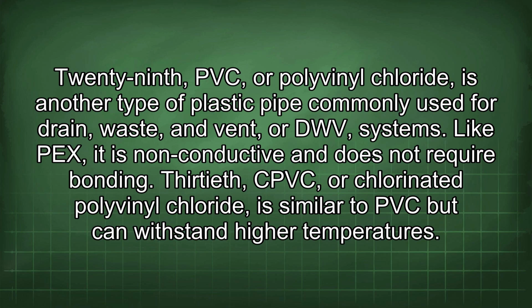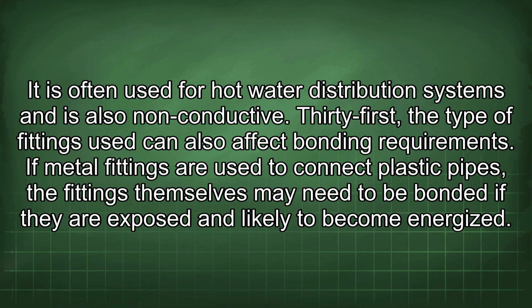30th, CPVC, or chlorinated polyvinyl chloride, is similar to PVC but can withstand higher temperatures. It is often used for hot water distribution systems and is also non-conductive. 31st, the type of fittings used can also affect bonding requirements. If metal fittings are used to connect plastic pipes, the fittings themselves may need to be bonded if they are exposed and likely to become energized.